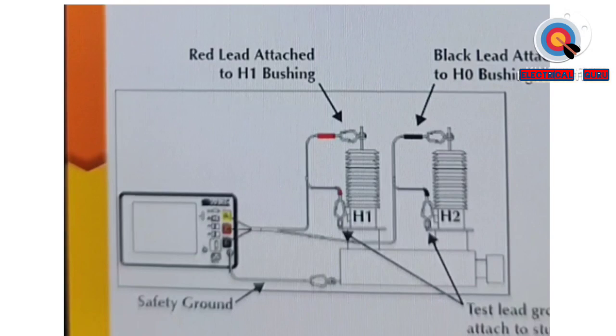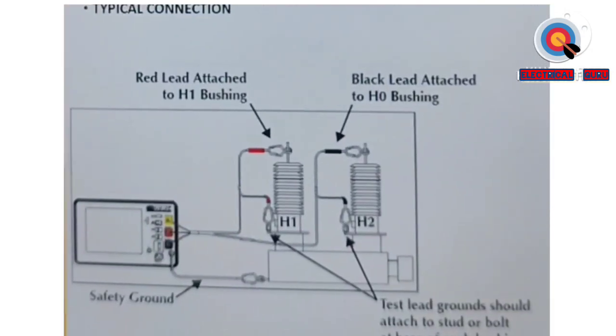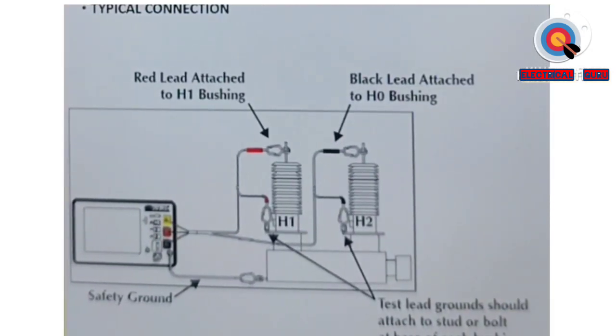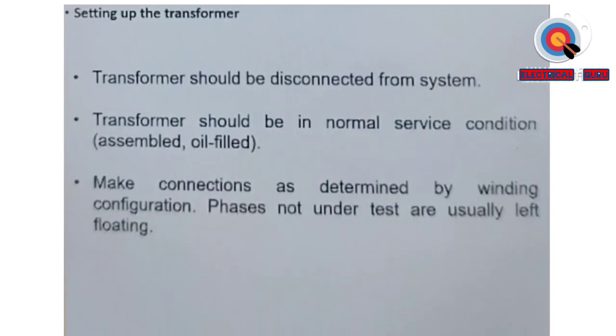On the high voltage side we inject the signal, on the low voltage side we check what is the output, and that input and output is given to the instrument, and the instrument has a built-in algorithm so that it will calculate 20 log V output upon V input, in terms of dB, and then it will plot a graph. Now before we start this test, the transformer should be disconnected from the system.